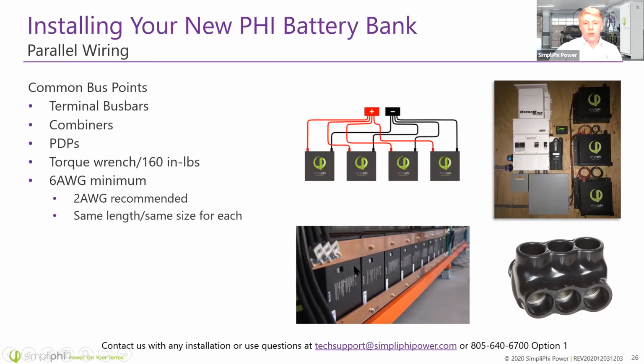Another method you can use is terminal bus bars. These big fat bus bars are super conductive, with very low impedance from one end to the other, which means they're great to lay directly on top of the terminals of the batteries, and then you can connect your inverter and charge controller wires directly to them. This was actually an 80 battery system at an airport hangar in Hawaii. Pretty cool project.